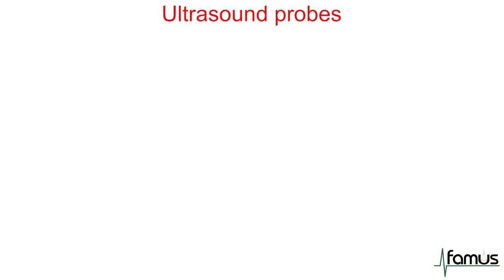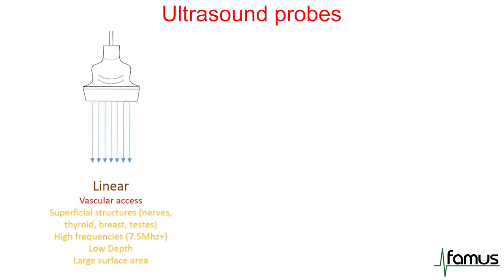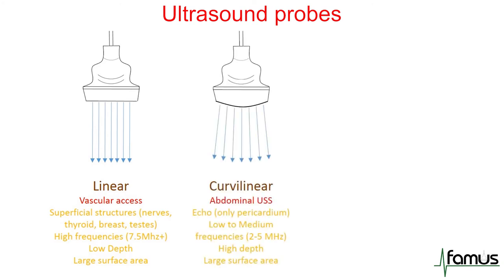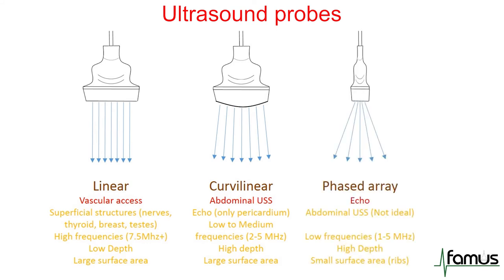Looking at point-of-care ultrasound transducers: linear transducers are high-frequency probes giving good resolution but limited depth, making them perfect for superficial structures like nerves, thyroid, breast tissue, and testicles — also used for vascular access. Curvilinear probes are ideal for abdominal ultrasound, being low-to-medium frequency and giving good depth and resolution. A phased array probe is mainly used in echocardiography, has a low frequency for good depth, and has a particularly small surface area.